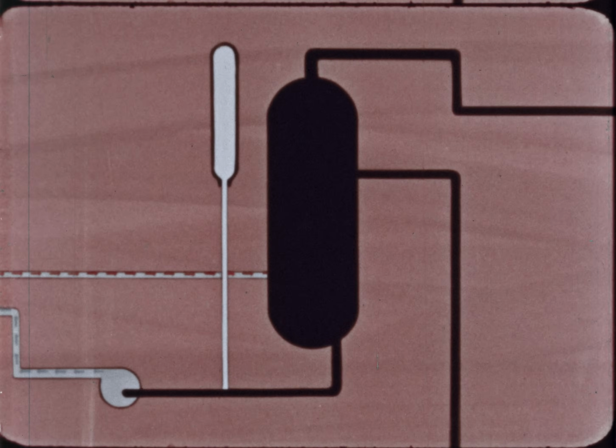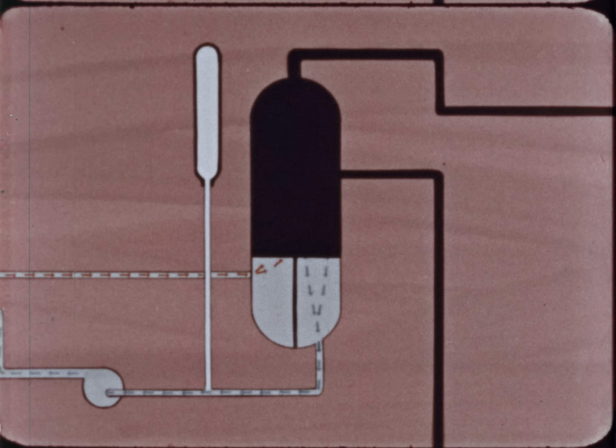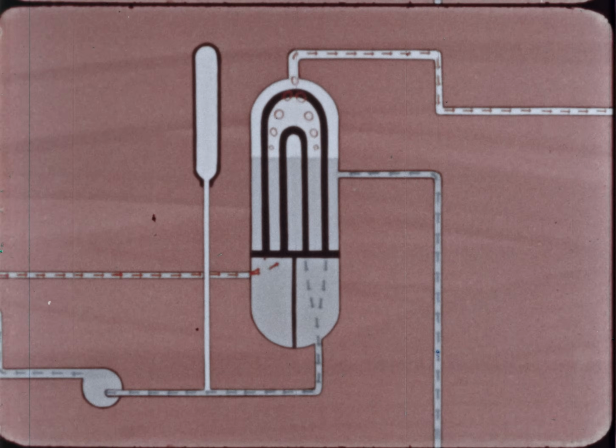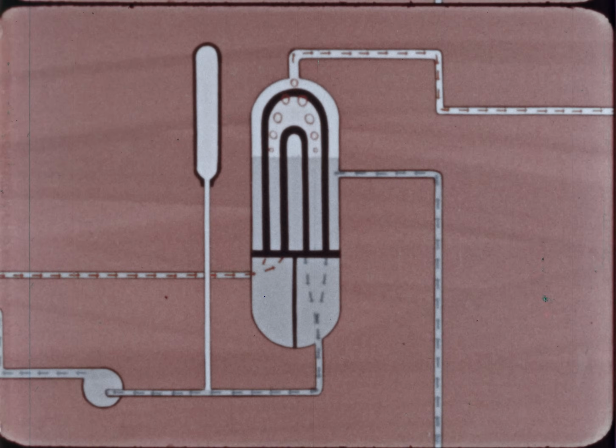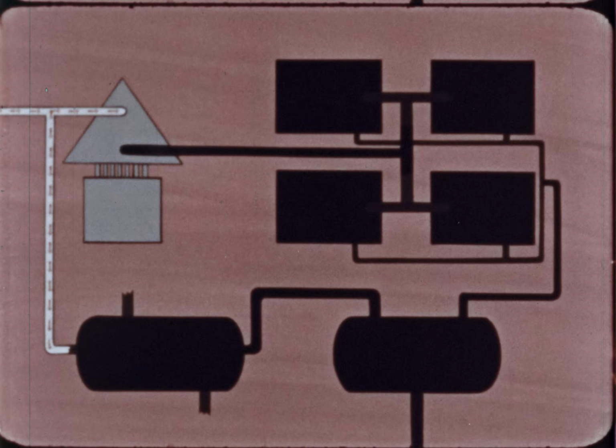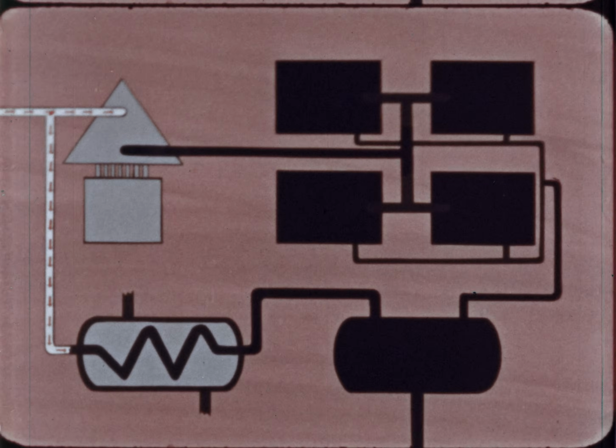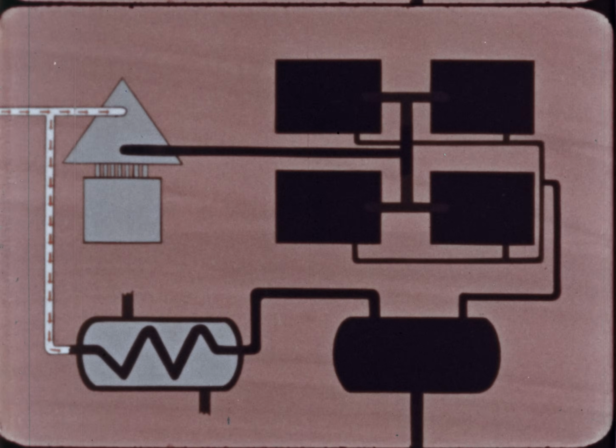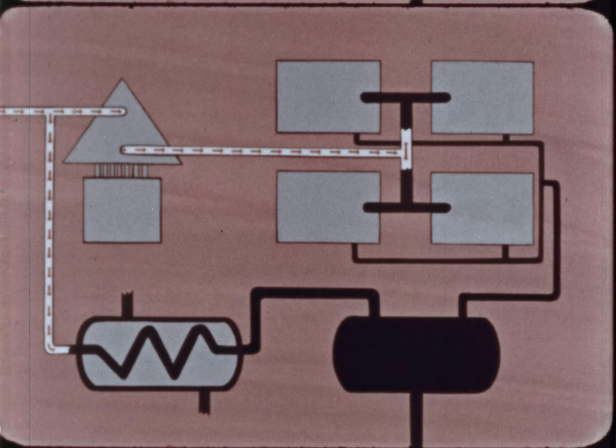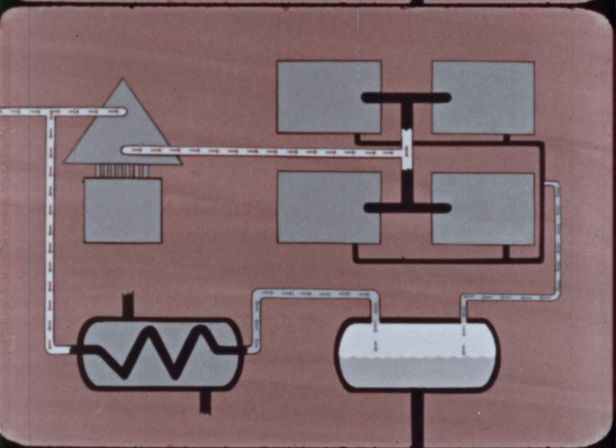As the primary water flows into the tube side of the steam generator, it gives up heat and flows out. Secondary feed water picks up that heat on the shell side and is released as dry steam. This steam drives a single extraction turbine generator and feeds the evaporator reboiler at the same time. Exhaust steam from the turbine flows to 4 air-to-steam condensers and is converted to water, which is drained to the hot well along with the evaporator condensate.